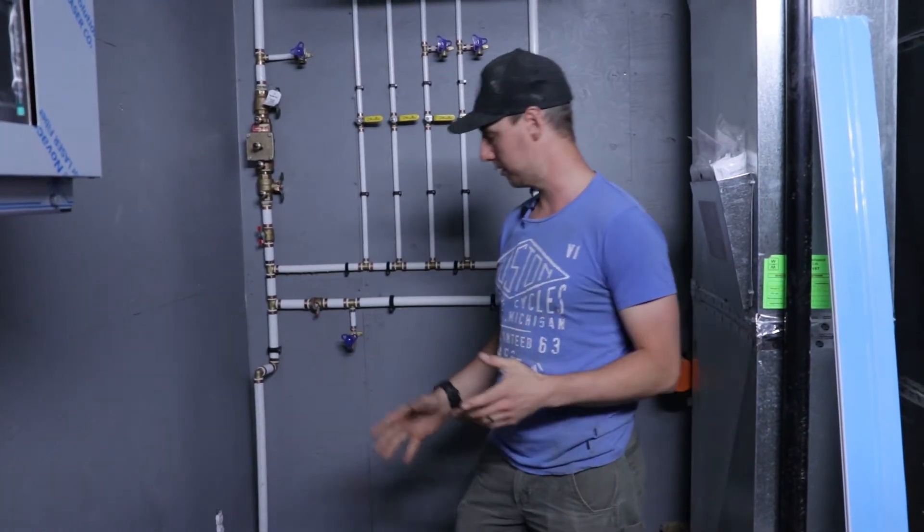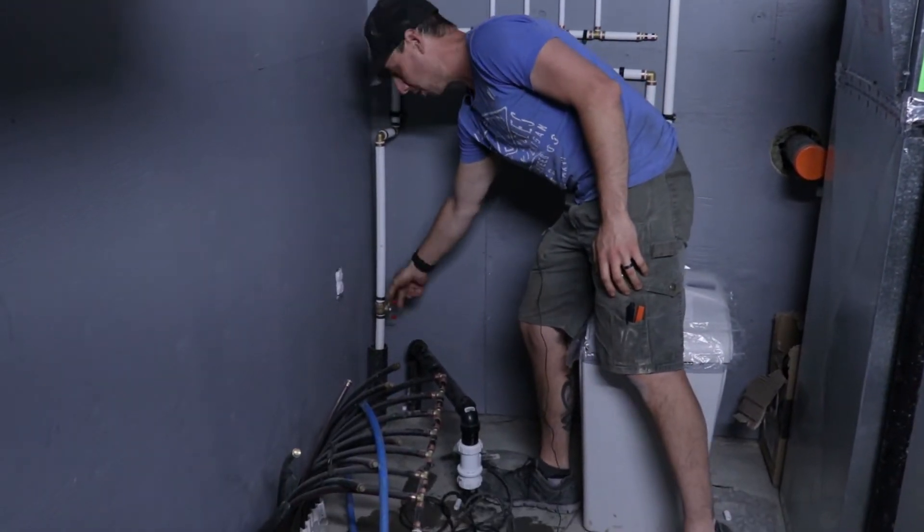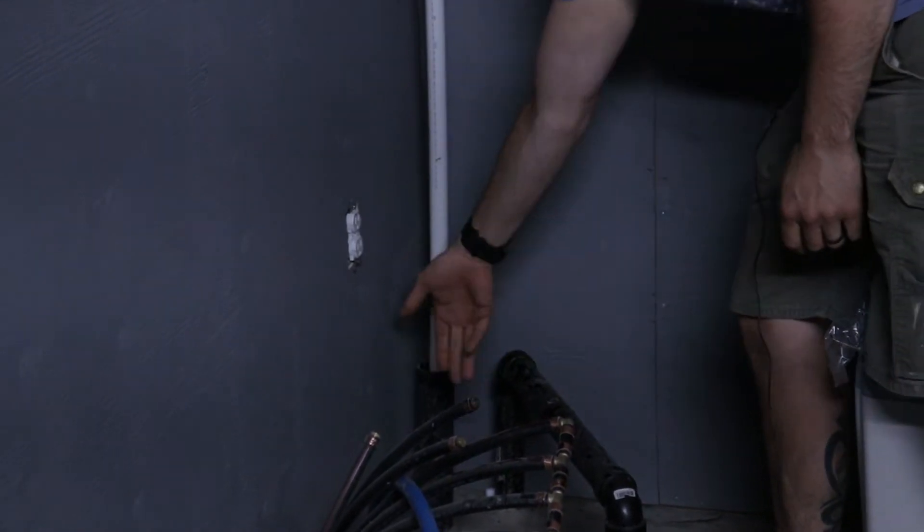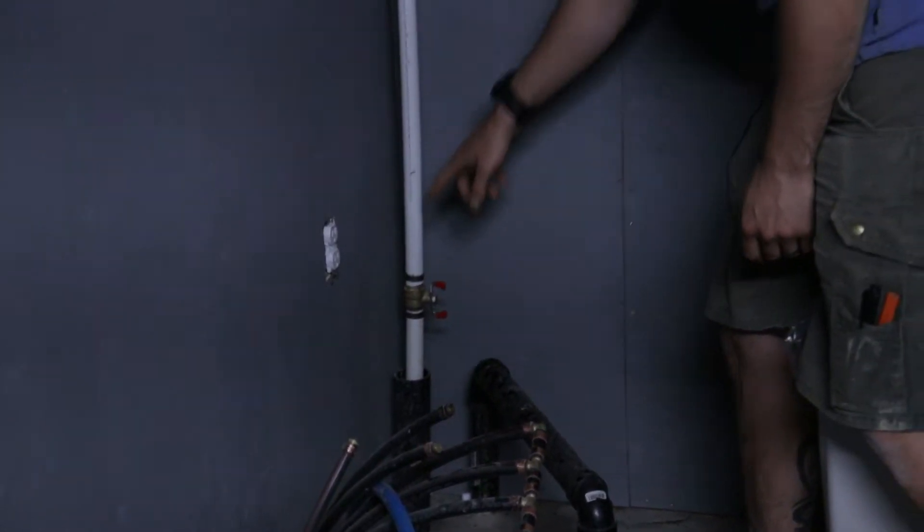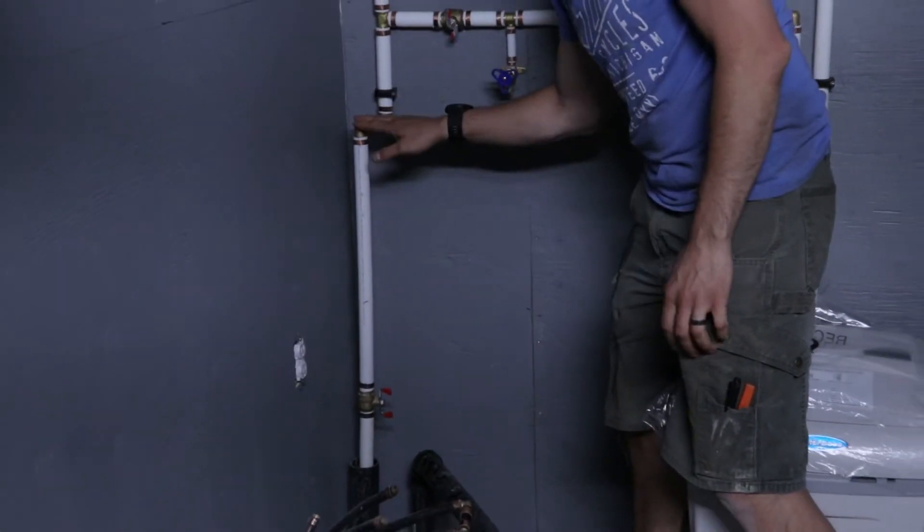The first thing we're going to talk about is where the water comes in. We have our main service coming up here with one inch pipe. We usually like to put our valve pretty low but not too low, just 12 inches off the ground with a sleeve under the concrete. We always like to leave a minimum of 18 inches before we do any fittings.